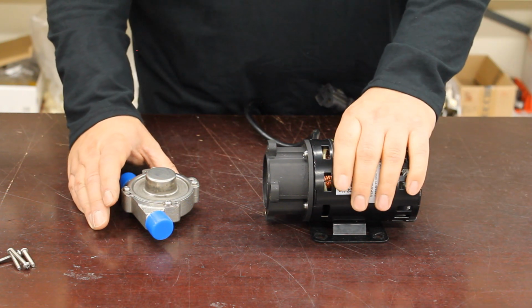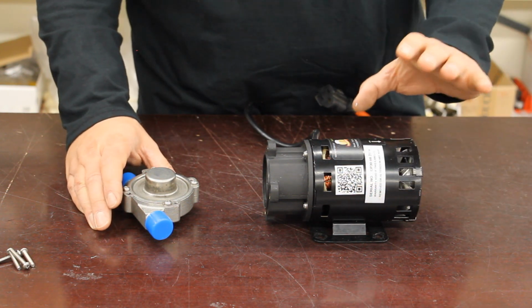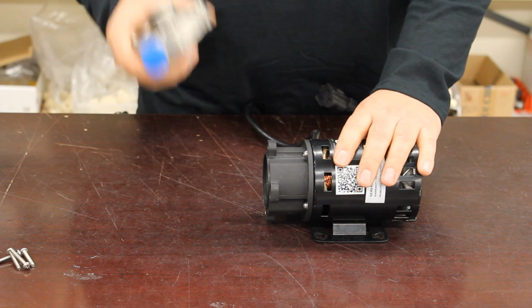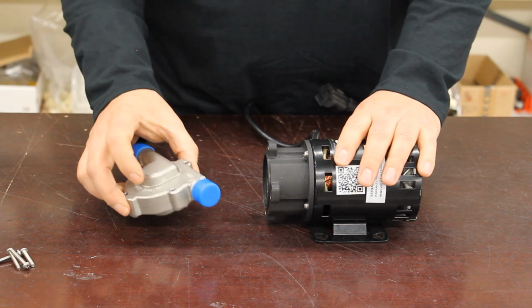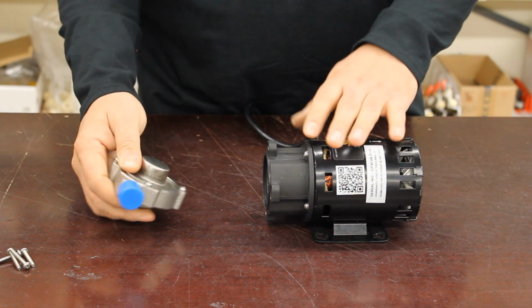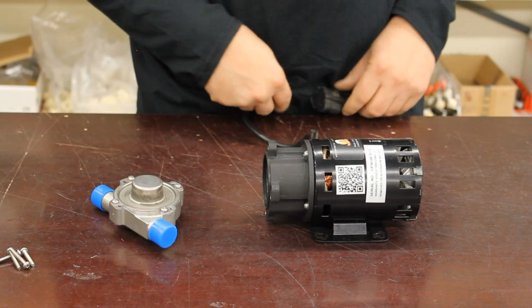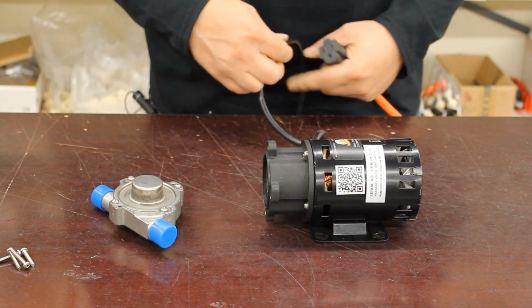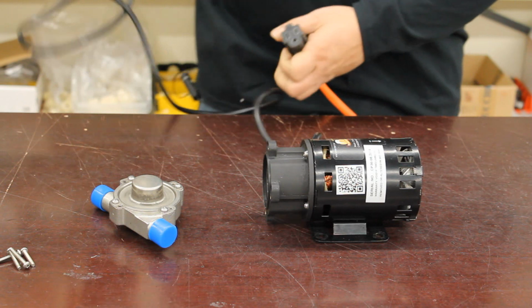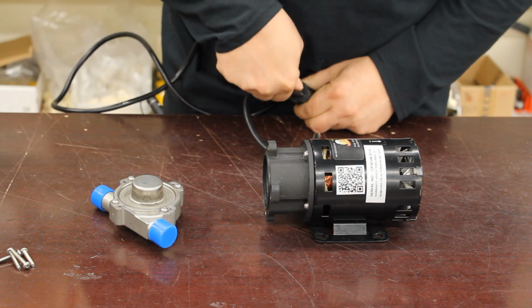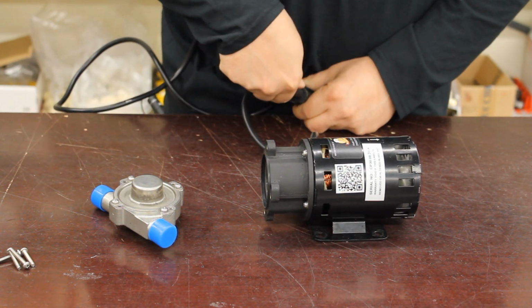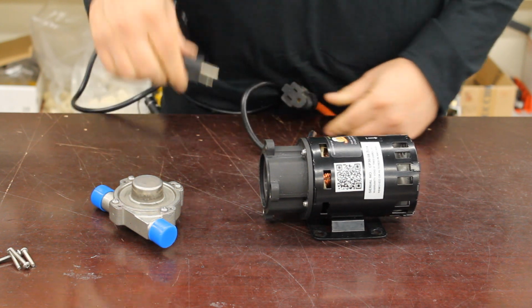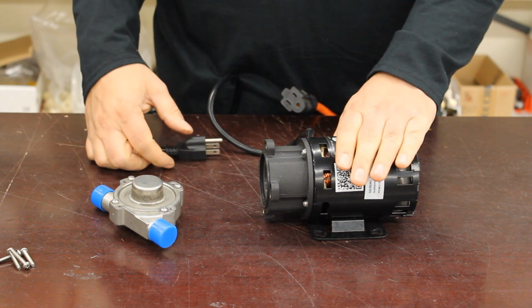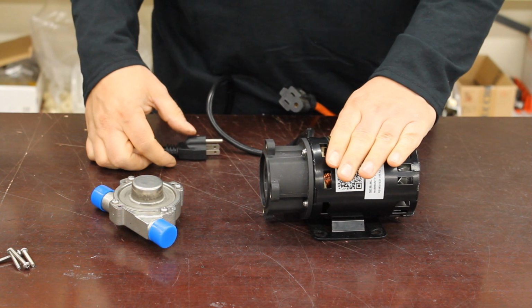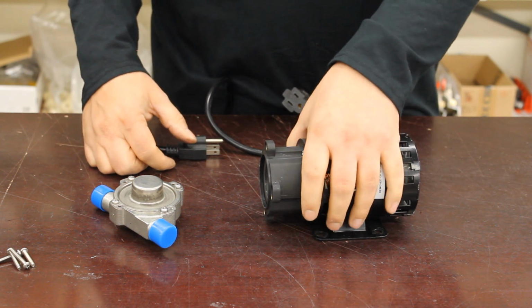Now, it could be a faulty motor, but most likely it's not. The first troubleshooting step is to remove the head using the 4 screws on the face of the head, like we've done here, and then go ahead and plug the pump in. All right, the fact that the motor is spinning freely means that the motor is not bad in and of itself. There must be something else going on.